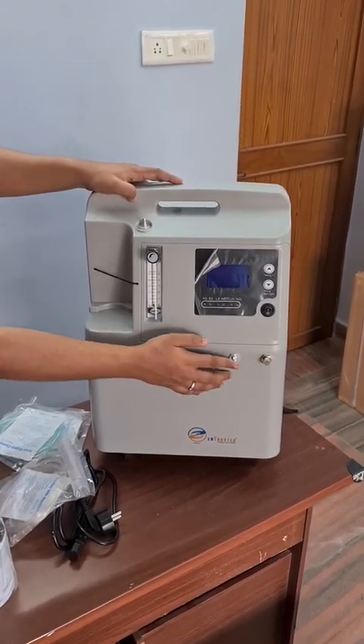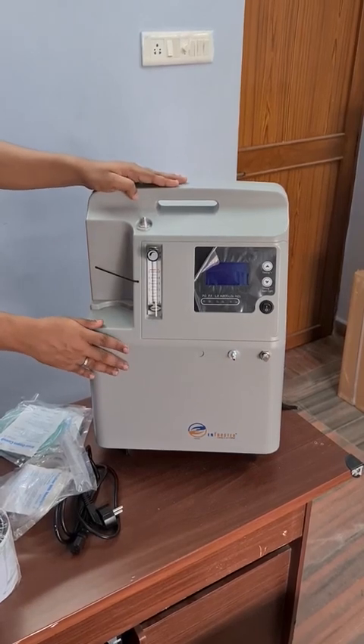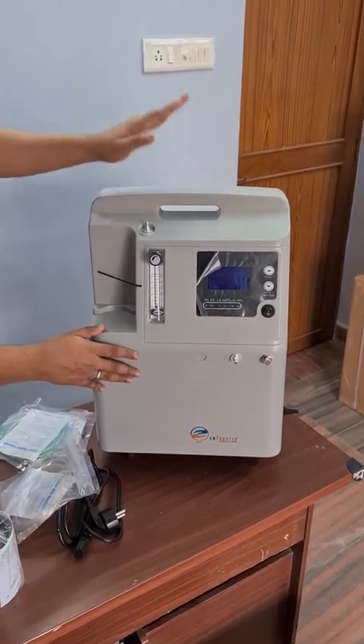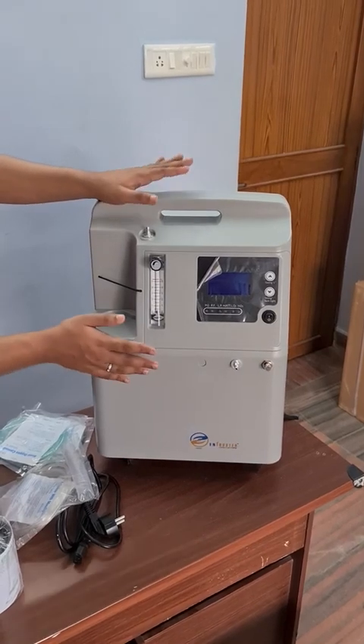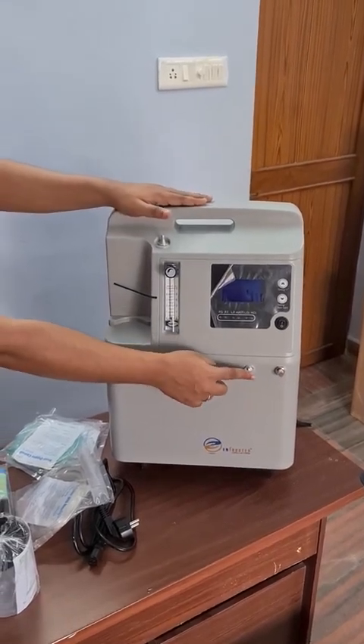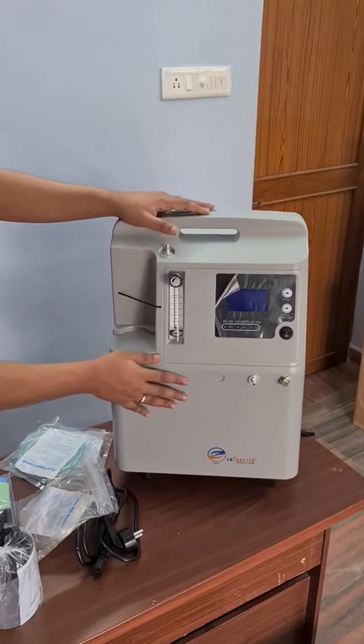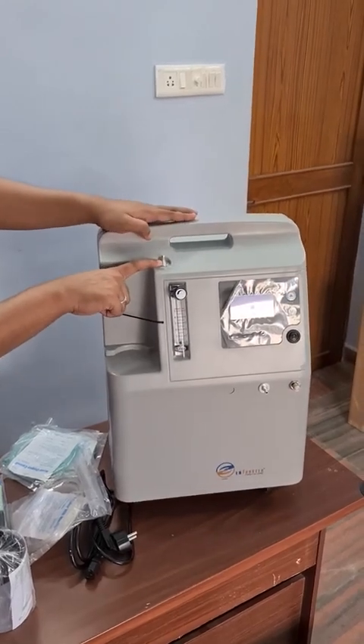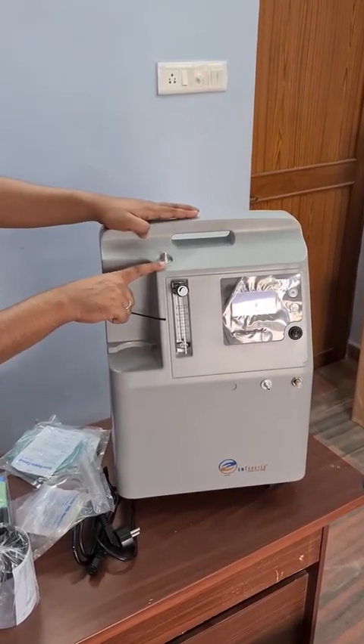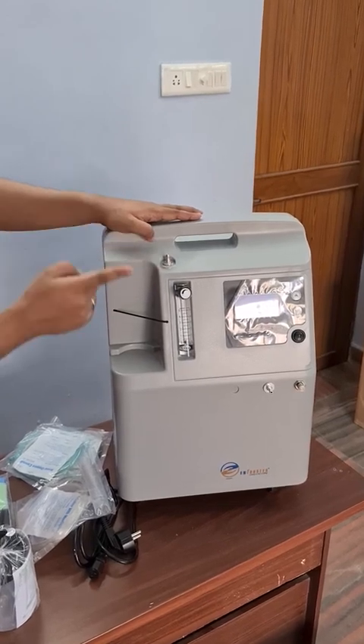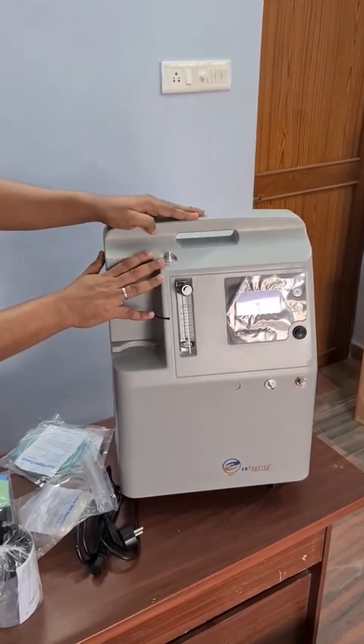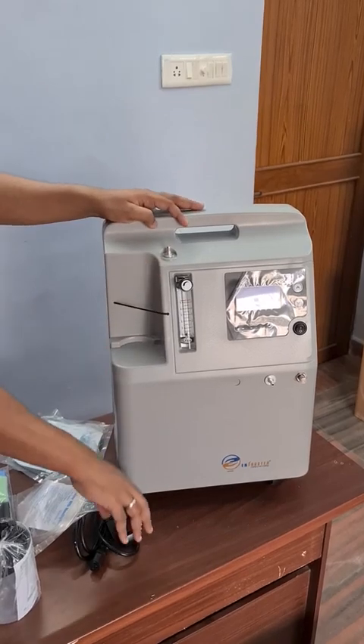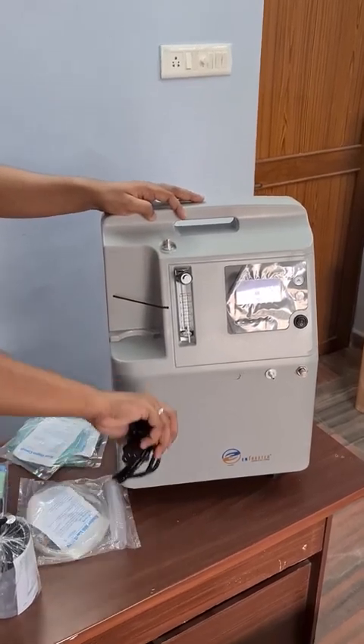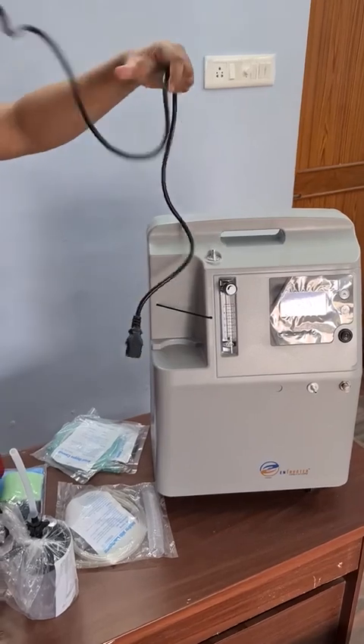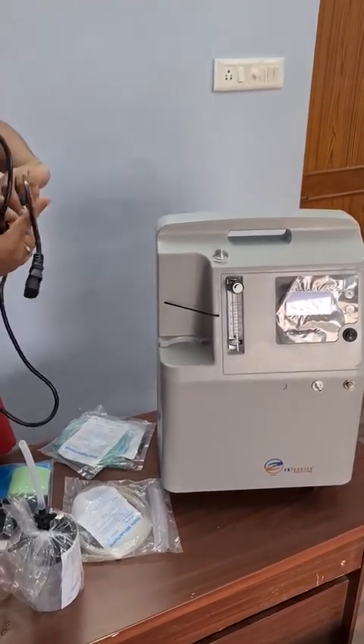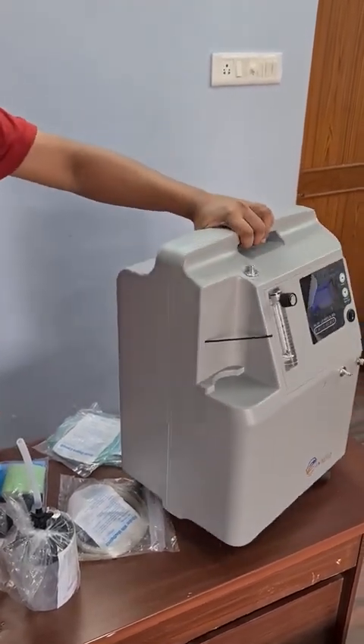And this is the port for nebulization. This concentrator can be used in two ways. You can use it for oxygenation, and when you are not using it for oxygen, you can use this optional port for nebulization. And this is the oxygen output port. Once you switch on the device, oxygen exits from this port only. That also I'll tell you in detail. Now I'm going to switch on the device. Switching on is very simple. We take the power cord and, just like any other electronic device, connect it.